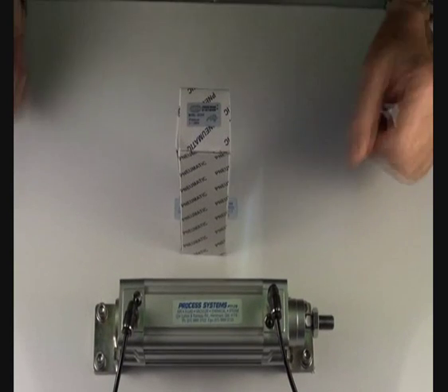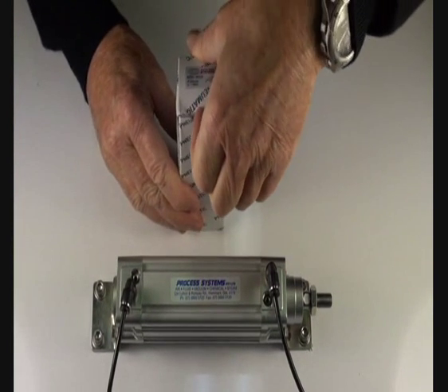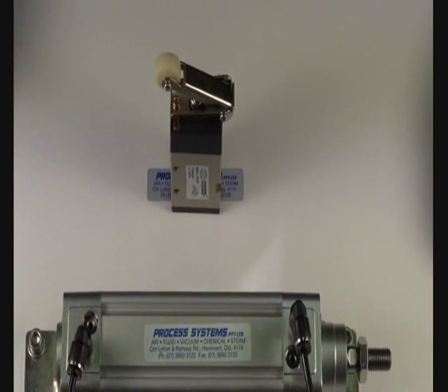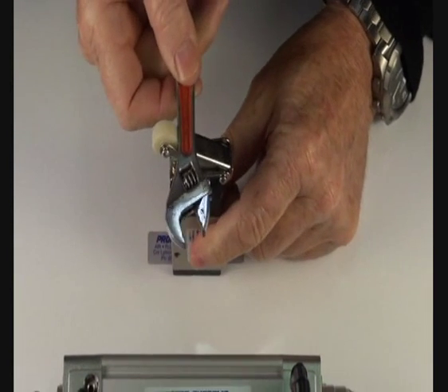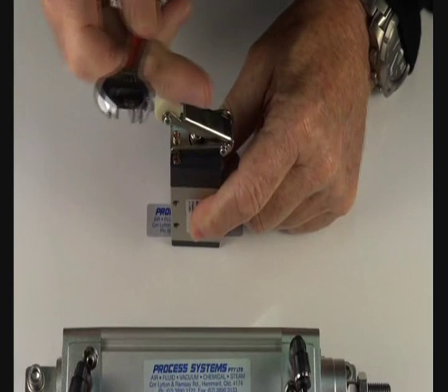Roller lever spring return valve, 5 port for operating double acting air rams. This valve is designed to be struck by a moving slide or machine coming along, depresses the valve as it hits. It's got the roller on the top, takes some movement out of it.